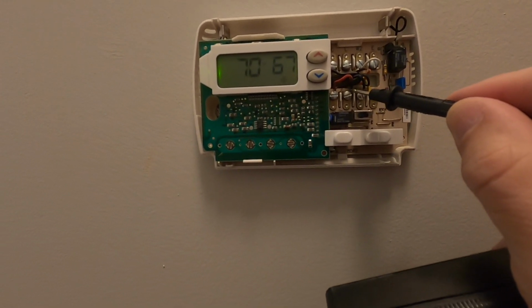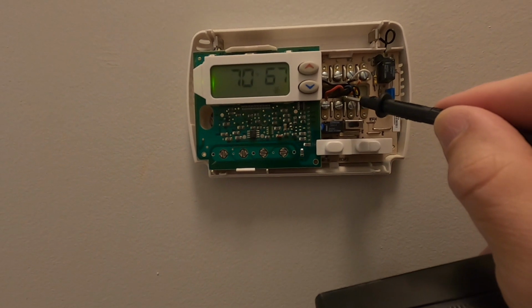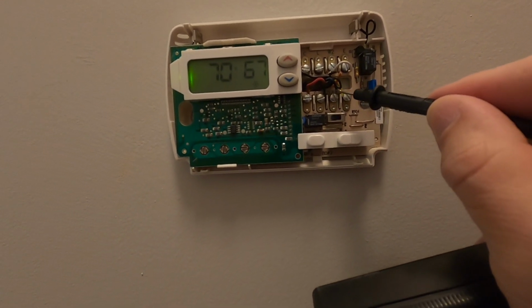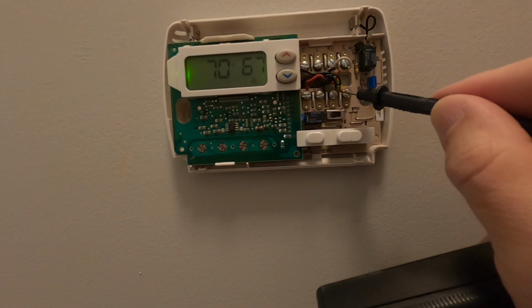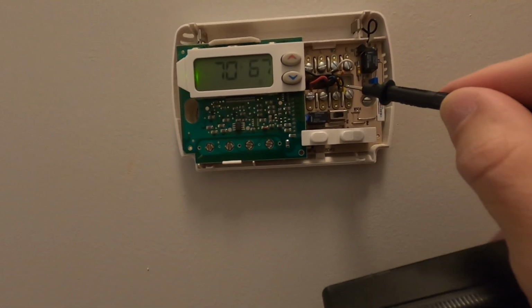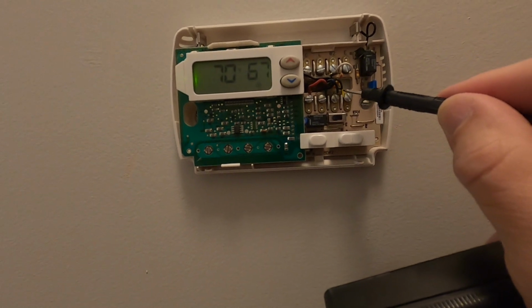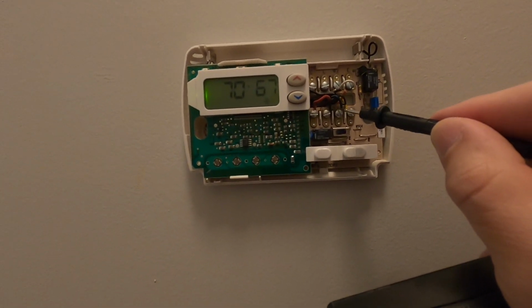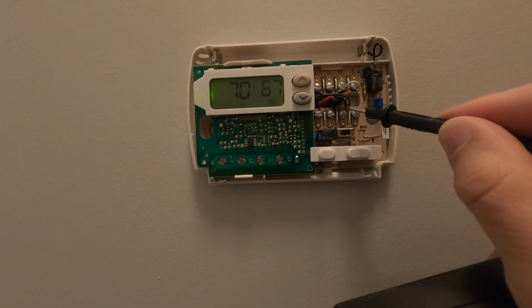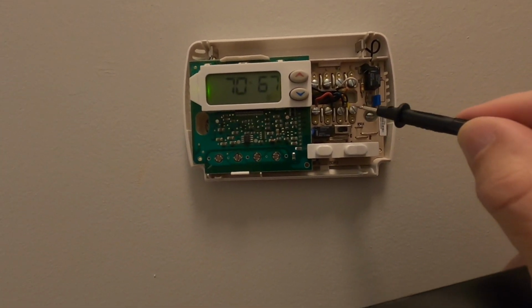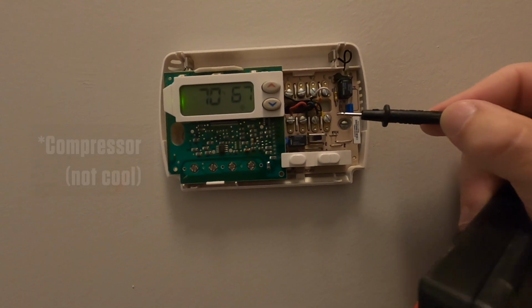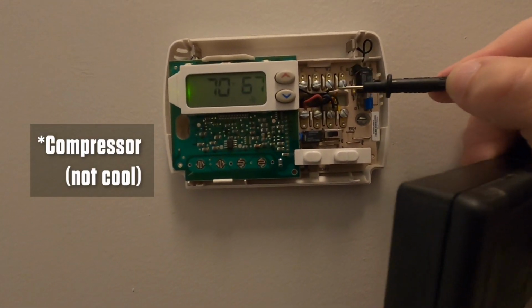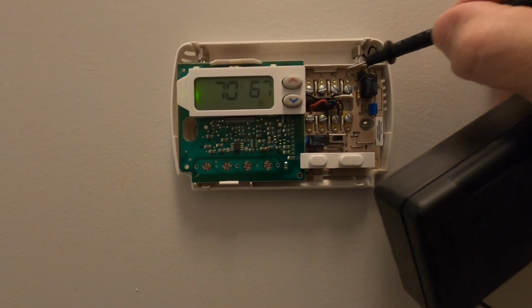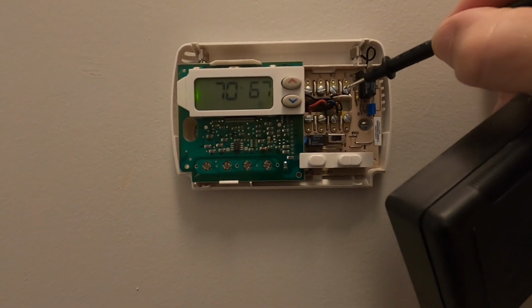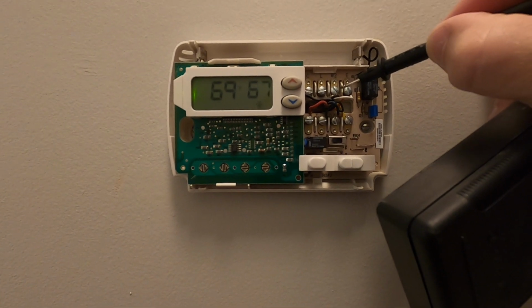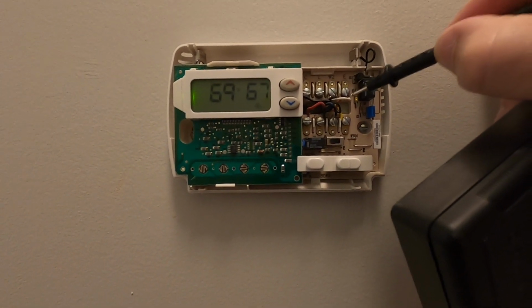G is for the fan that blows air through your house. O or B, depending on your unit, relates to heat pumps—that's the reversing valve. Depending on the brand of heat pump you have, most work one way, but Rheems, which I have, work the opposite in terms of whether that engages during heat or cool. Yellow calls for cool, and white—notice these are jumped, white or W2 to E for emergency heat—brings on the electric heating elements downstairs in the furnace.